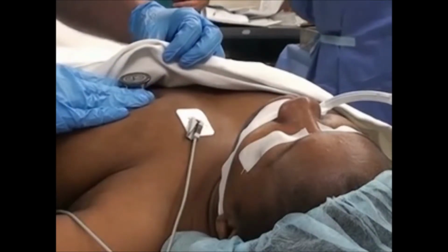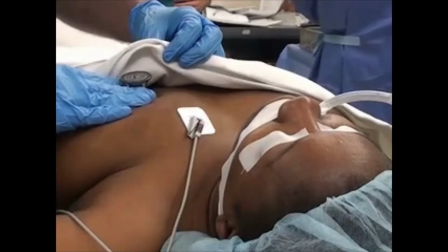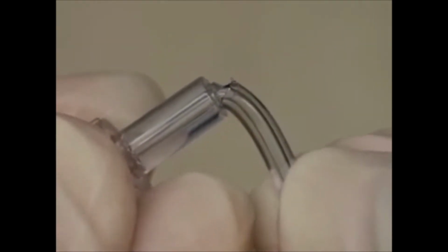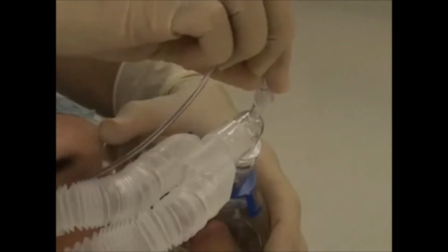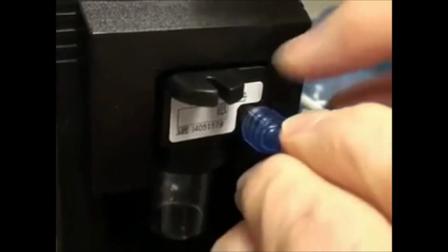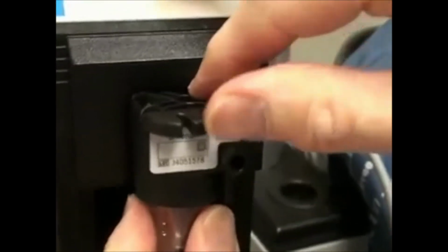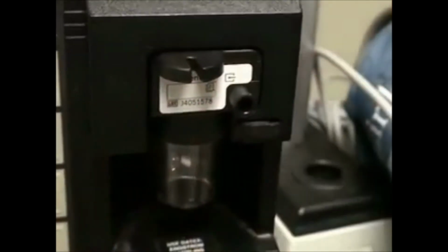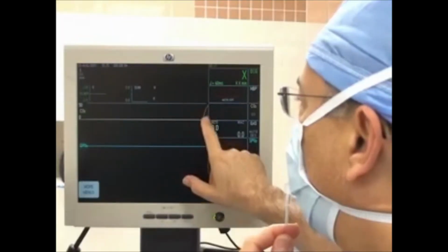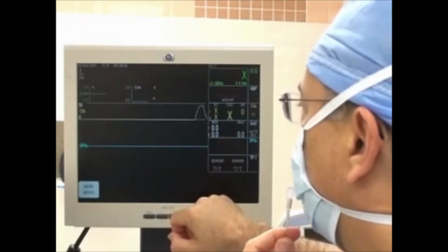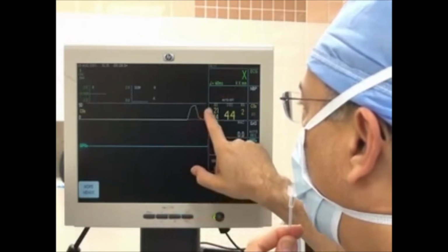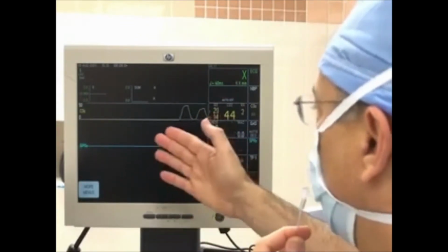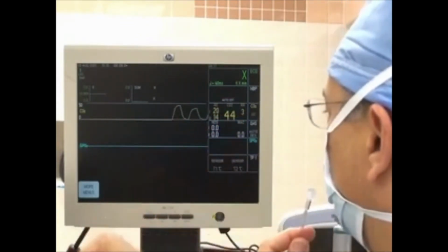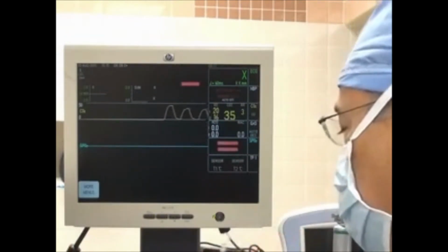If the patient appears to be clinically stable, consider the possibility of either leakage or occlusion of the sampling system. Make sure that the side stream sampling line is well connected to the circuit and to the water trap on the capnograph, and that the water trap is firmly attached to the capnograph. To quickly test the integrity of the sampling line and monitor, breathe into the sampling line. A waveform confirms proper sampling, although small leaks diluting the sampled gas may go unnoticed.